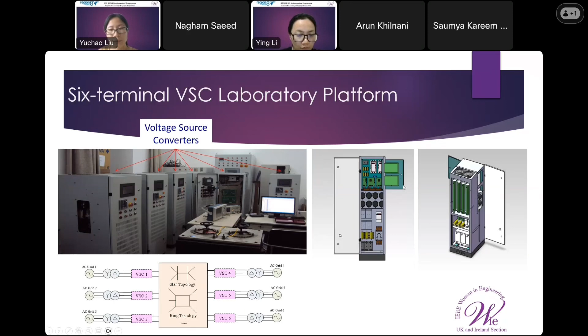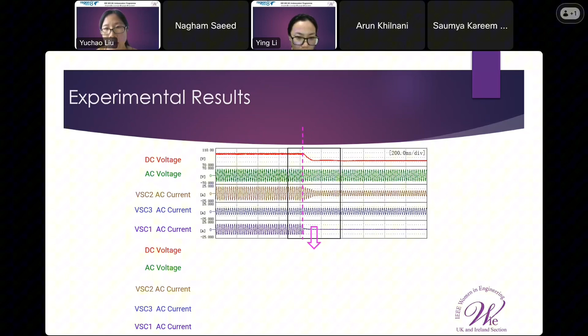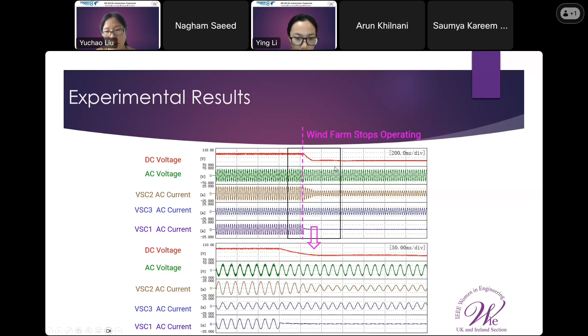We also did some experiments based on the multi-terminal HVDC. One of the most important principles for MTDC is the N-1 principle, meaning at any time if any one terminal, any one farm or grid, stops operating, the rest of the power system, the MTDC, will still keep operating. For example here, when one of the wind farms stopped operating, after a few milliseconds the whole system reached a new stable operating mode, because the power supply reduced causing the DC voltage to drop, but then it reached a new balanced operation mode.